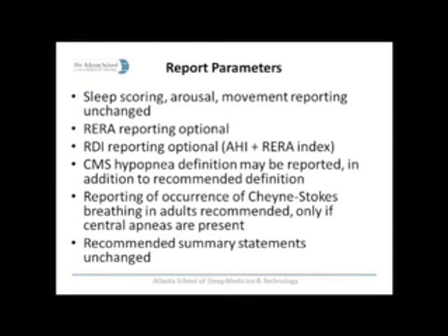The recommended filter settings for each set of parameters are also unchanged from the scoring manual, with the additional note that nasal pressure signal should be processed either through a DC amplifier or AC amplifier. If through an AC amplifier, with a low frequency filter setting of no more than 0.03 hertz. The other typical recommended low frequency filter settings for other respiratory channels would be 0.1 hertz.